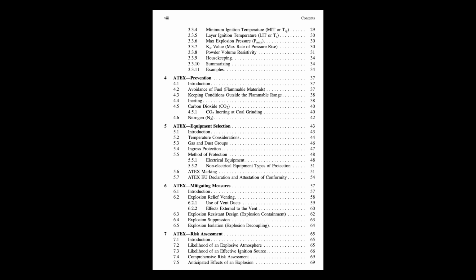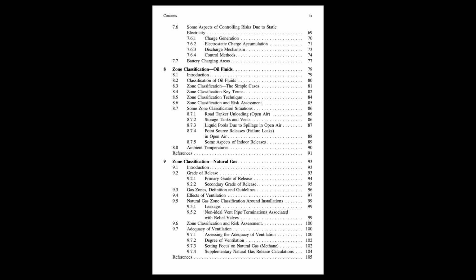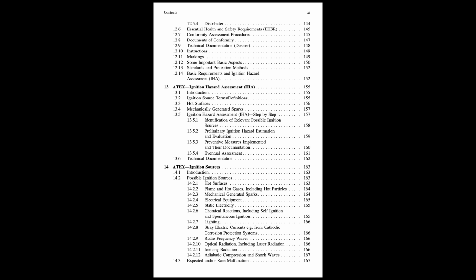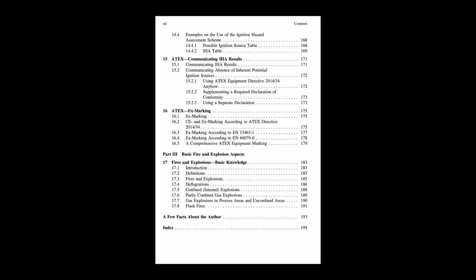Exactly. The second method is to control the concentration. If you do have flammable substances, you make sure their concentration in the air stays well outside the explosive range. So either too little fuel or too much fuel. Precisely. Keep it below the lower explosive limit, the LEL, that's too lean to burn, or keep it above the upper explosive limit, the UEL, that's too rich, not enough oxygen mixed in. The LEL and UEL, so those are like the boundaries of the danger zone, yeah? That's a great way to put it. Below LEL, not enough fuel. Above UEL, not enough oxygen. Bang in the middle, that's where the danger lies.